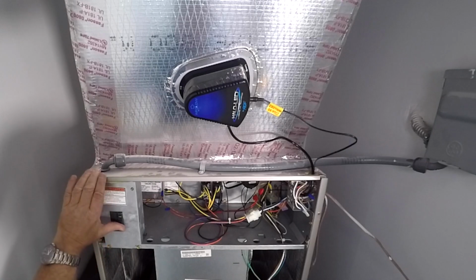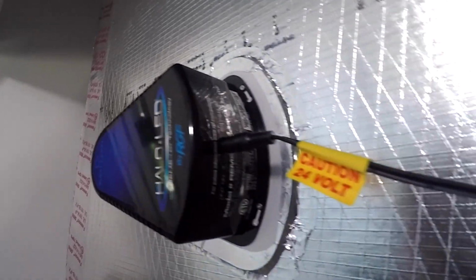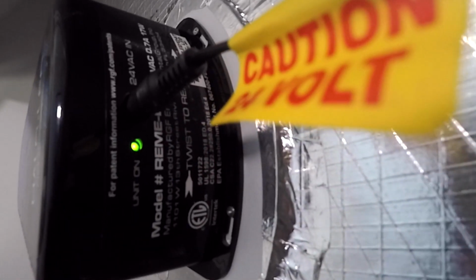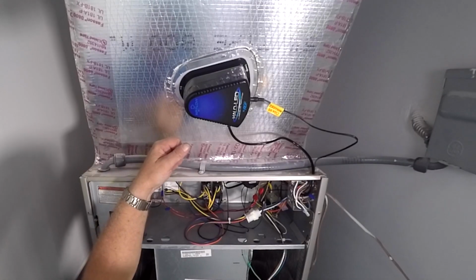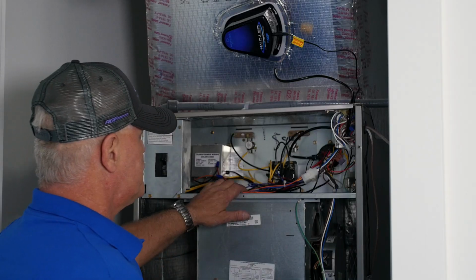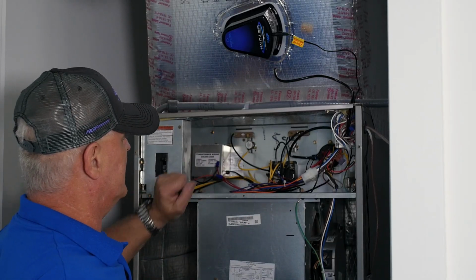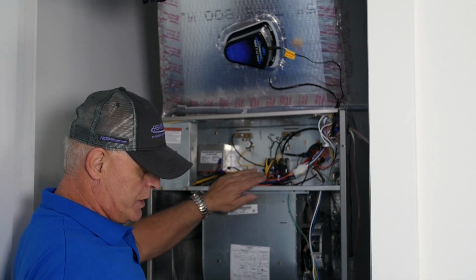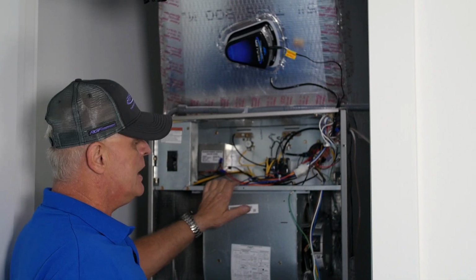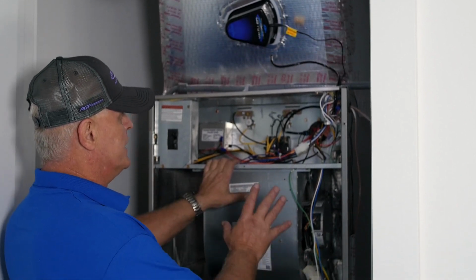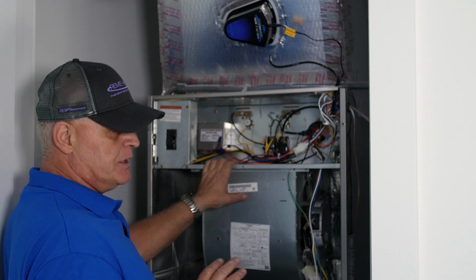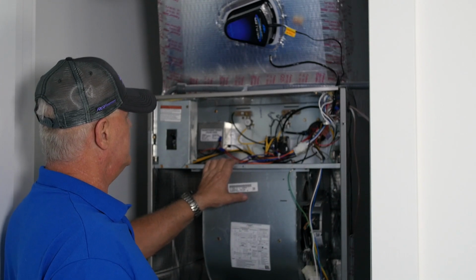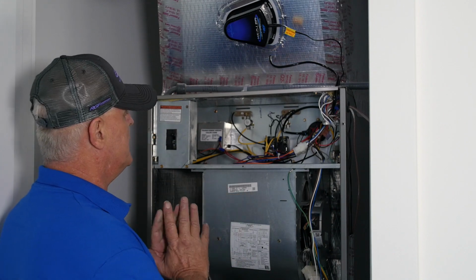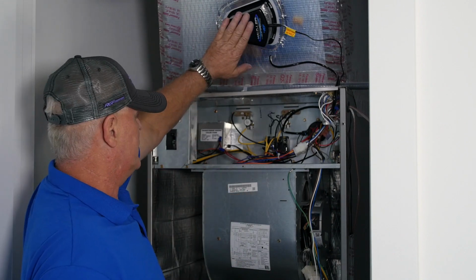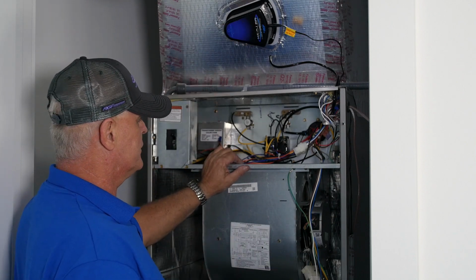Now, all we need to do is power the unit up and turn the blower on, and you will hear the unit come on. As you hear the buzz and you see the little wire light come on, we now have a finished running unit using the air switch. This unit is a standard unit which does not have any electronics in it, so the air switch for this unit is a very simple and quick install, as well as this can be used on any unit in this style. It does not care whether it is an electronically communicating unit, whether it has a 2-speed blower, whatever. Anytime the blower comes on, the LED unit will come on. Anytime the blower turns off, it will turn off.